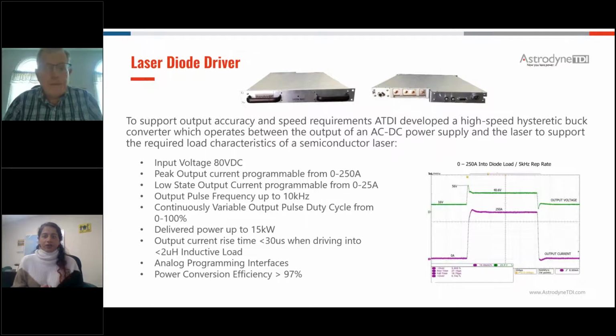In a semiconductor laser, you have a string of light emitting diodes, and in order to increase the current in those diodes, you need to increase the voltage across them. Typically you might have to go from somewhere around 15 to 20 volts up to somewhere around 40 to 45 volts to increase the current from very light to very heavy. To do that quickly, the output voltage of the power supply has to increase quickly.